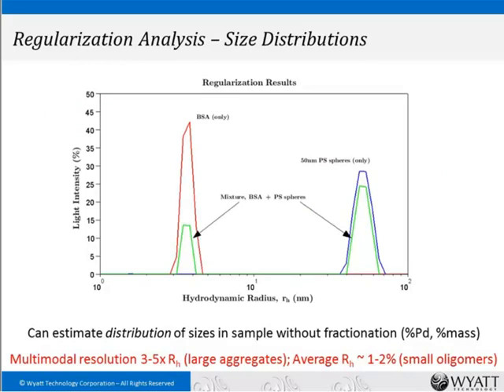Here's an example of regularization results: a mixture of BSA and polystyrene spheres. Measured individually, BSA appears at about 4 nanometers and the polystyrene spheres at about 50 nanometers. Mixed together, you can see these distinct peaks. Note that the size scale is logarithmic — to differentiate populations, their physical radius needs to differ by about a factor of 3 to 5. It's not a high-resolution technique, but quick and easy for identifying larger aggregates, with average RH accurate to 1–2%.